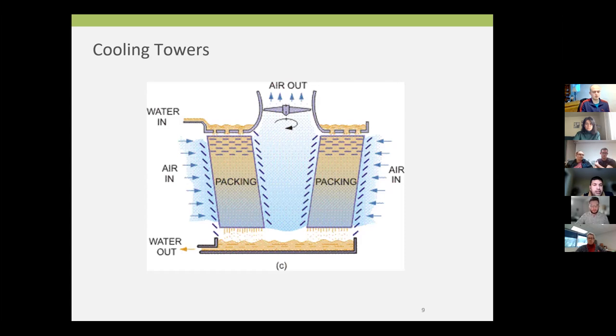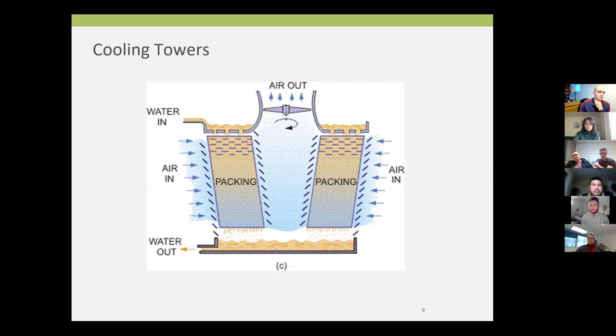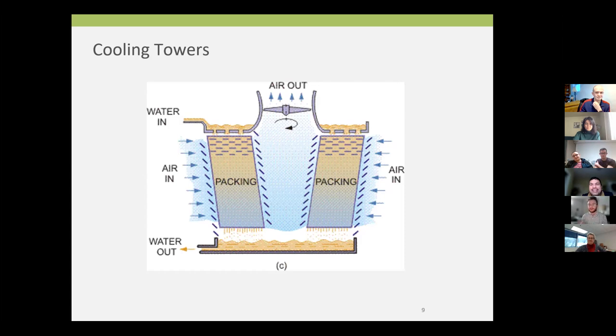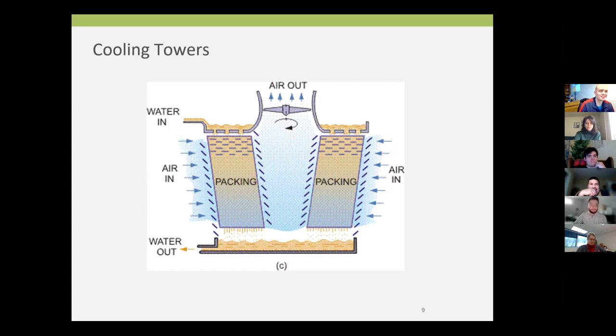There's lots of ways to improve the performance of your cooling towers and save energy by leveraging what you value more. You value chemical treatment more. You value electrical energy more. It's going to vary from customer to customer. In many cases, the cost of chemical can exceed the cost of electricity. So, they may opt for using more electricity and less chemical. I know the focus typically for my company for the IAC is electric, but when you sit down and have a conversation with the property owner, they may come to you and say, no, we don't like that because the cost of chemical is 10x, or that we have to do filtration of the water, and that kills us. Another thing going on in Utah right now with the drought that we've faced is that the move away from cooling towers to air-cooled condensers is a very valid recommendation. And now you're actually going to increase energy use because you don't have the advantage of wet bulb temperature. You're working on dry bulb, but we have a more precious commodity that we care about in a drought condition, water. So, you may, in some of your audits, find some resistance to water-cooled condensers. There's nothing more efficient than water-cooled towers. Don't get me wrong, but there's the opposite side of it, the reality of it that you have to be aware of as well.